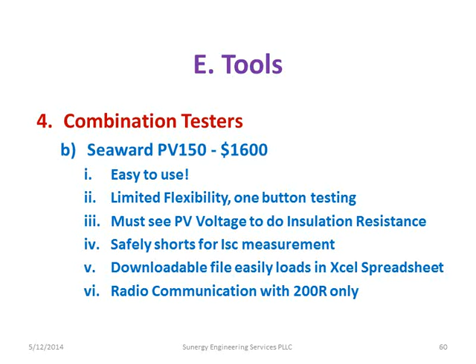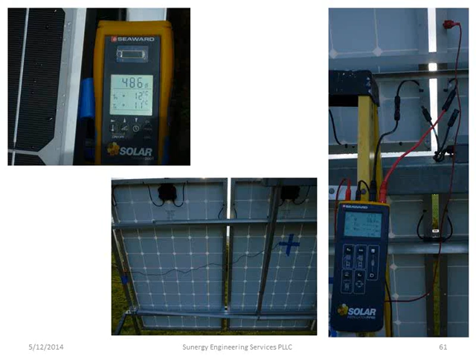Now the other one, so basically you put your sensor up by the module, you get your temperature readings, that's radioed back to this guy, and then you can see the sensor just taped on the back of the module here, the temperature sensor, and then basically you just plug into your string. This is a single string here, so I plug directly into it, and you can get your whole test done right there. You can do ground continuity, and then you can go ahead and do the final test. It's just one button, does the whole test. So it's really quick. And that's not a bad price point, I think, for getting the irradiance meter and the temperature probe and everything together with it.